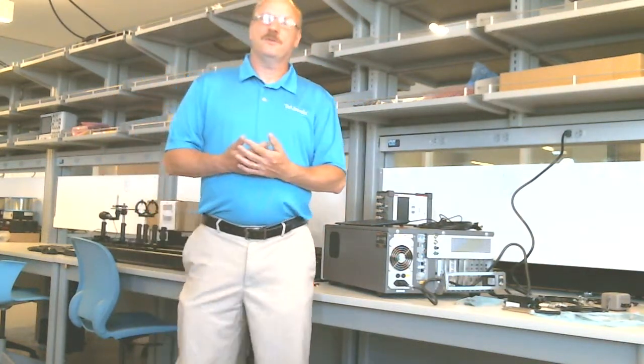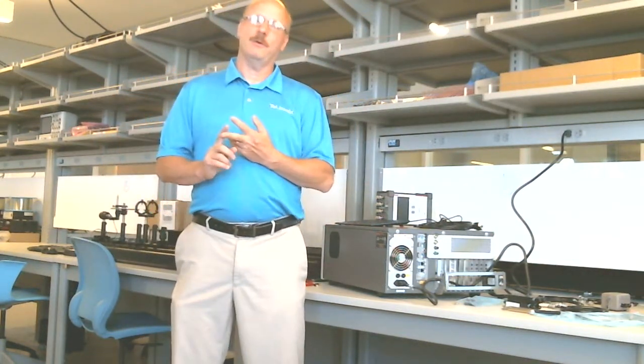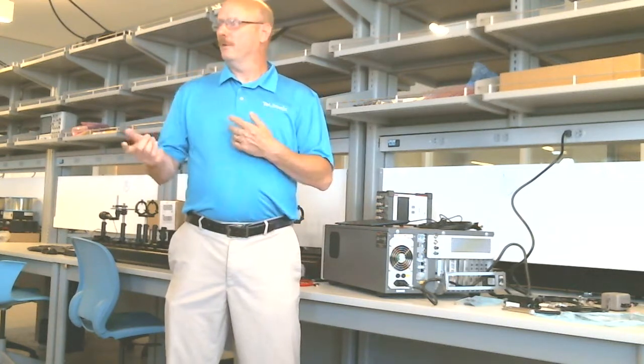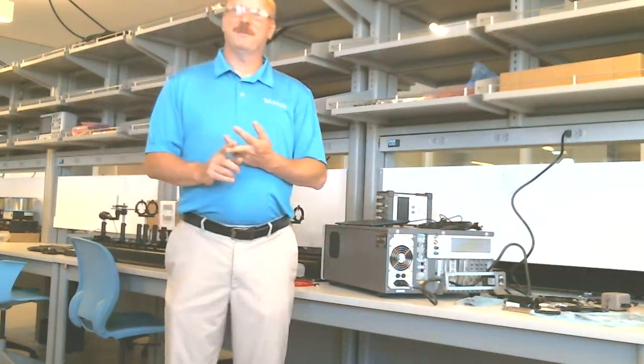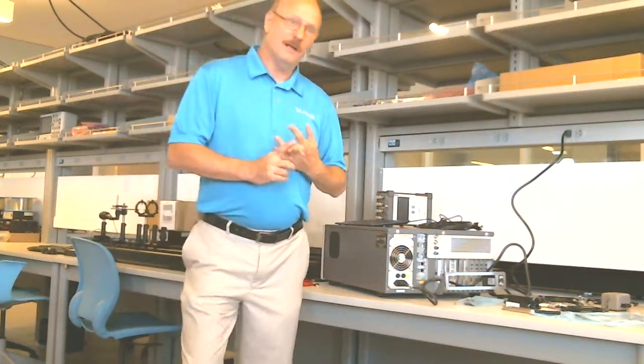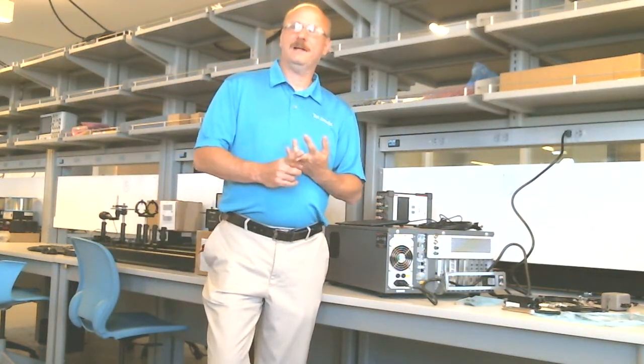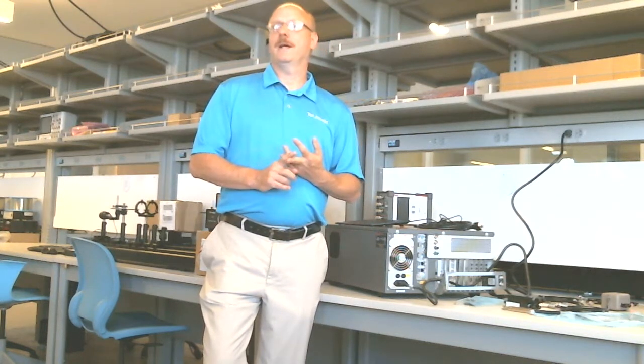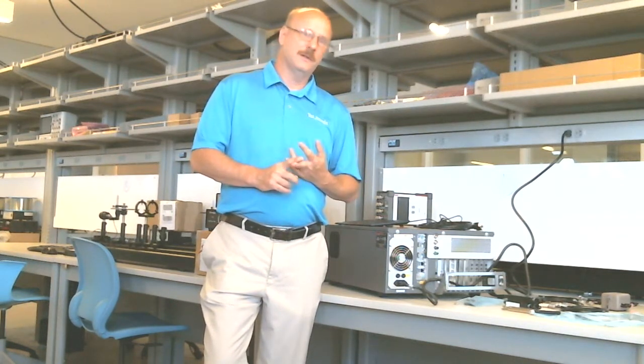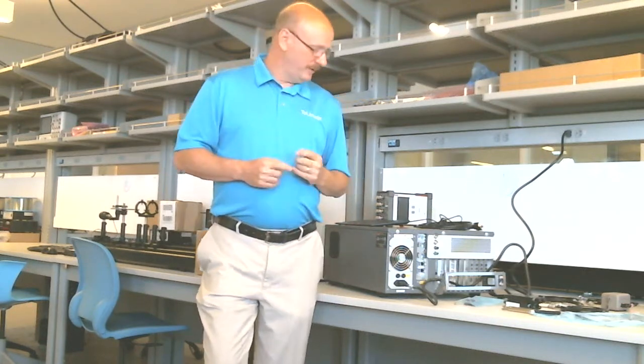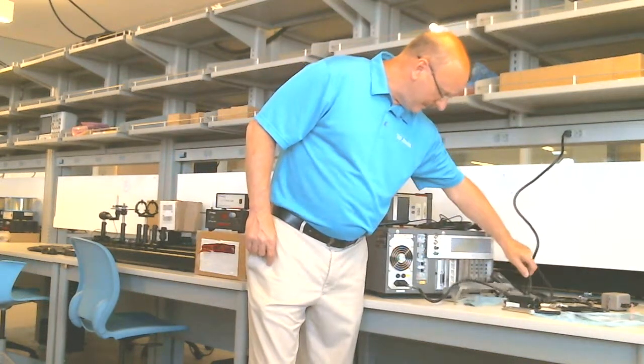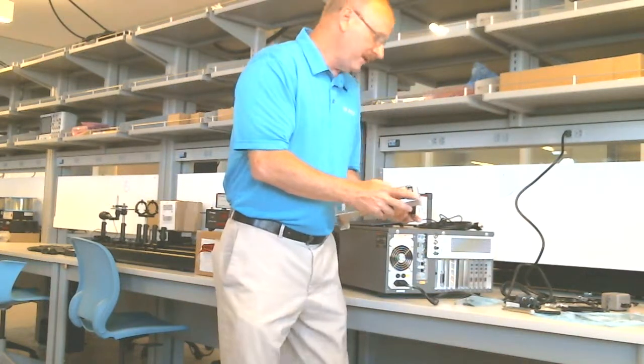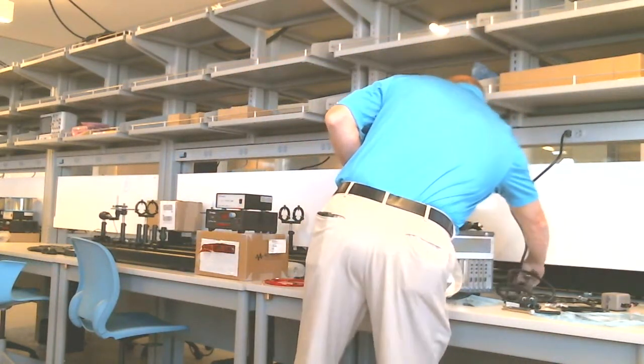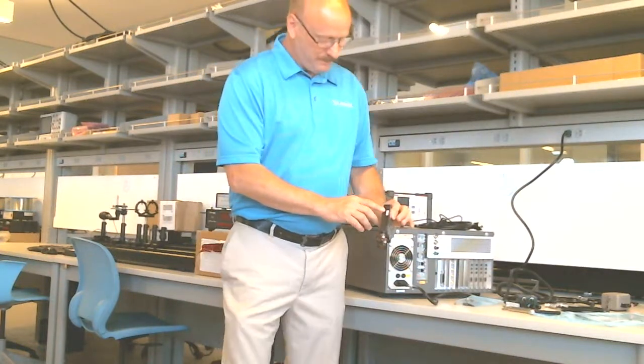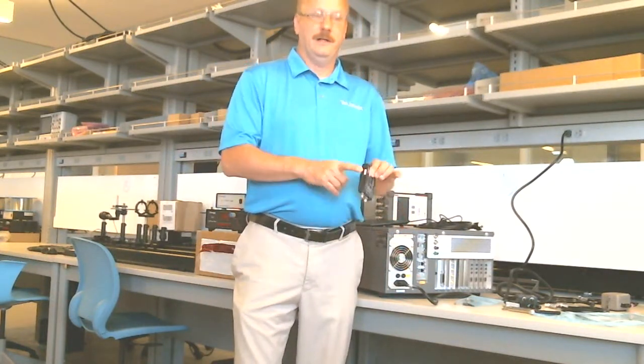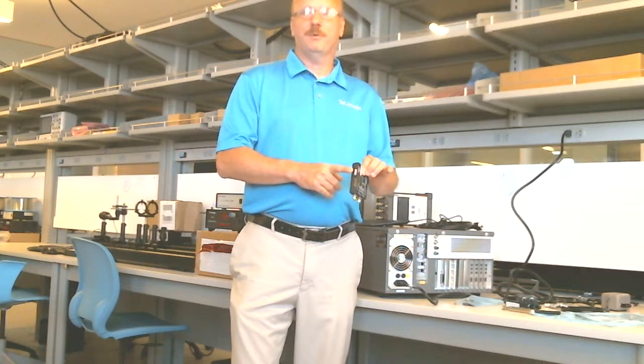There are 2 different SMUs. There's what we call medium power, and there's high power. You've got medium power. I don't know why we don't call it low power. But the specs of the SMUs you have are 200 volts DC max and 100 milliamps max on all 4 channels. Now, you'll also notice one of your SMUs has a preamp, which I've got connected. So we're going to take that off of there. Now, the preamp is marked SMU1. That's very important. It only goes to SMU1. You can't put this anywhere else.